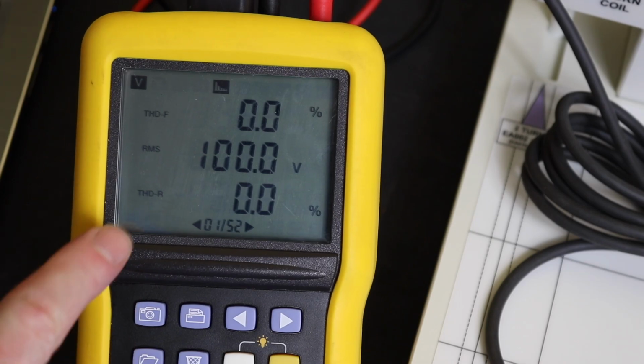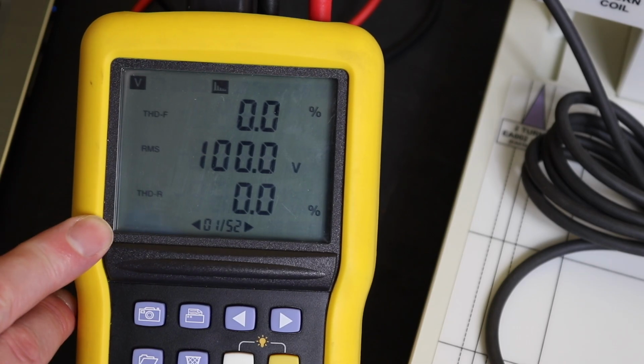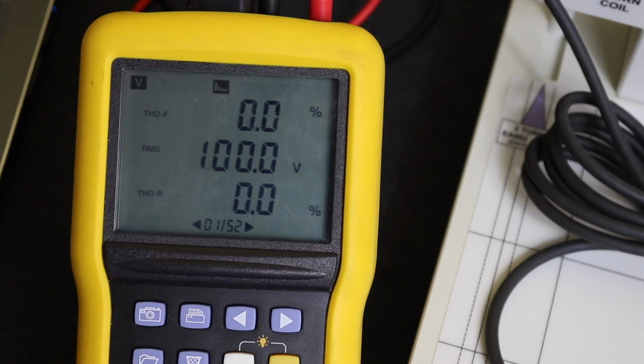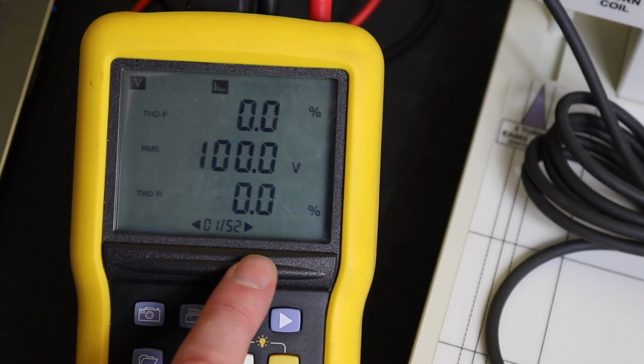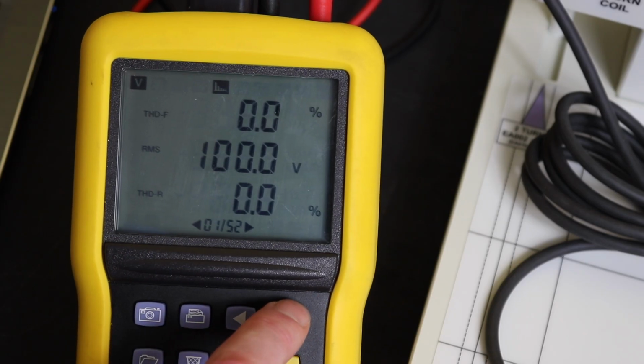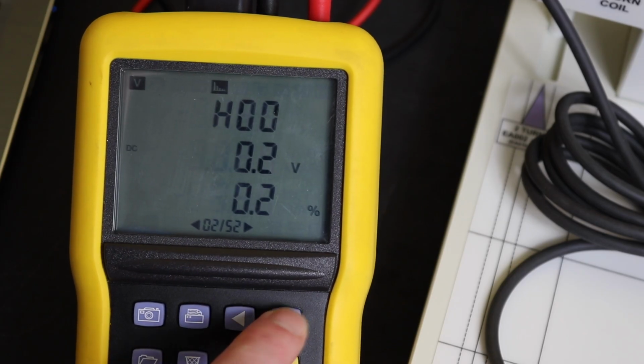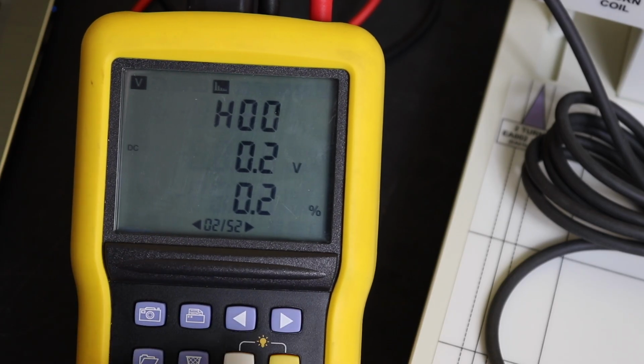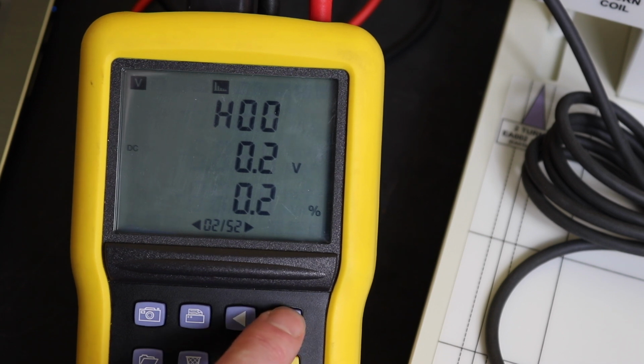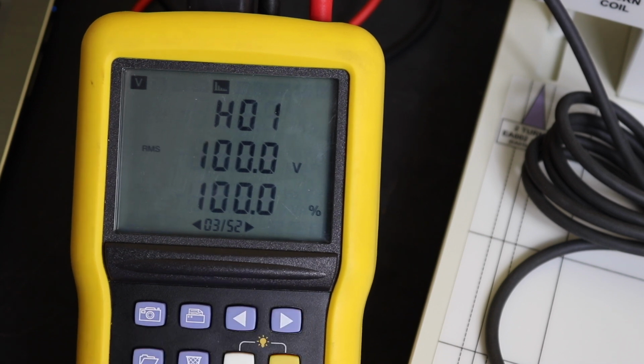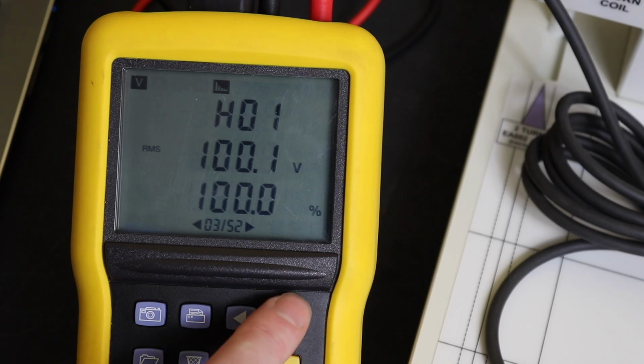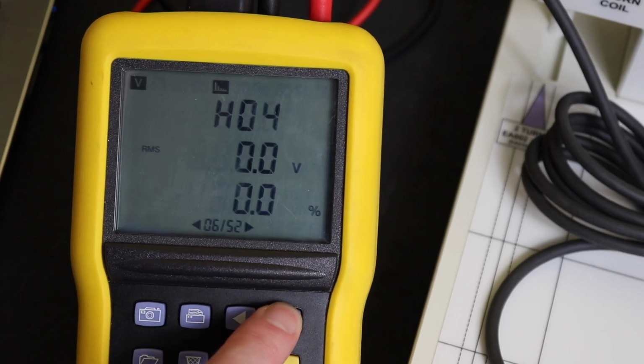Currently we're reading 100 volts. Our THD, total harmonic distortion, is 0%. Shows you how good this test set is, I guess. We've got 52 screens on this because this can read up to the 50th harmonic. So we then have our DC harmonic, which is virtually zilch, and then our harmonic number 1, which is our fundamental 50 Hz, is 100%, and everything else will be on 0 on this.